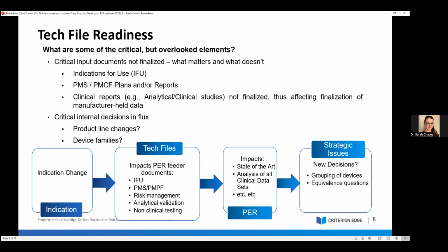So think about whether or not you need to undergo some additional design validations. For many devices that are going in under the IVDR for the first time and are legacy devices, they're noticing for the first time that they may not be state of the art and their design may need additional validations or tweaks to it. So that can also lead to some potentially unanticipated project delays.